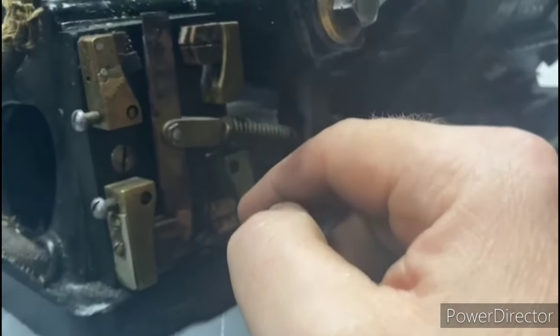Two other quick things before we get started: I forgot to mention that it is missing its nameplate. I'm going to call upon my friend Tom Utley over at Vaughn Industrial to fabricate us a new one — he really does outstanding work, and if you recall, he made the plate for the FS Betts motor we restored some time ago. Also, somebody has ground several different divots in this piece here. There's supposed to be one — the purpose is to engage the lever so it stays in position while it's in start mode, then you advance it to run mode. It looks like they were having difficulty finding a sweet spot to get it to run, probably because of all the arcing and sparking. So those divots are too deep and it catches too much, requiring too much force to move forward.